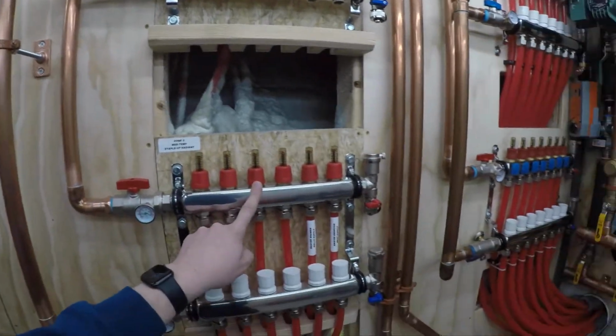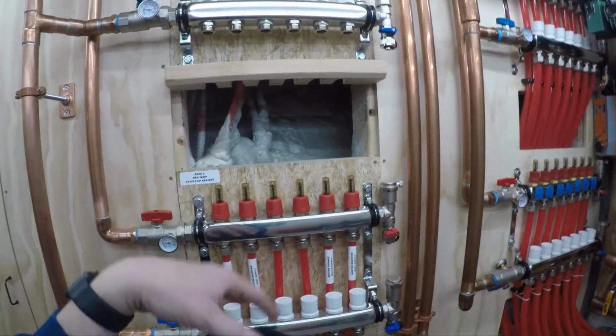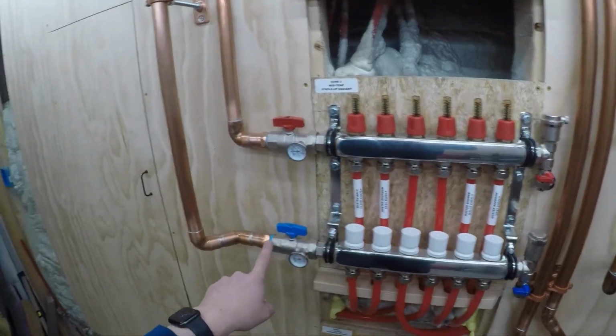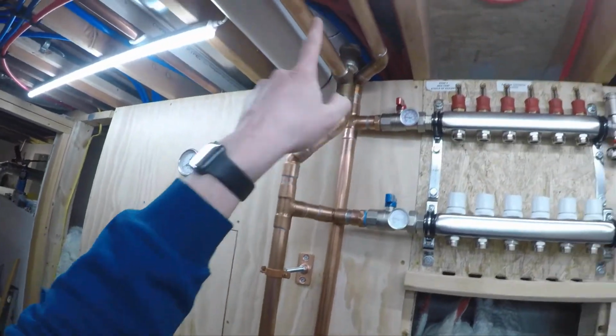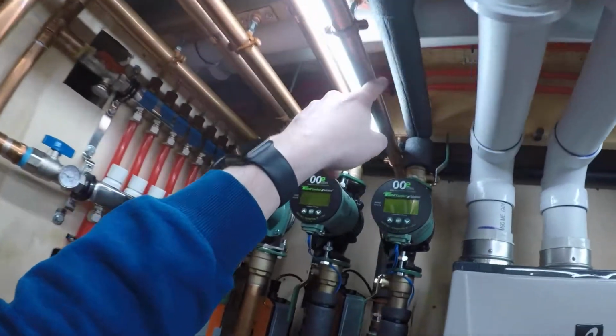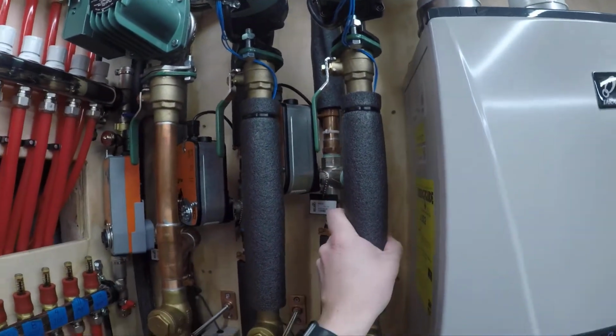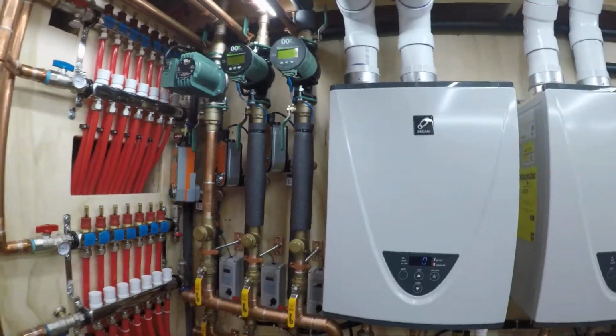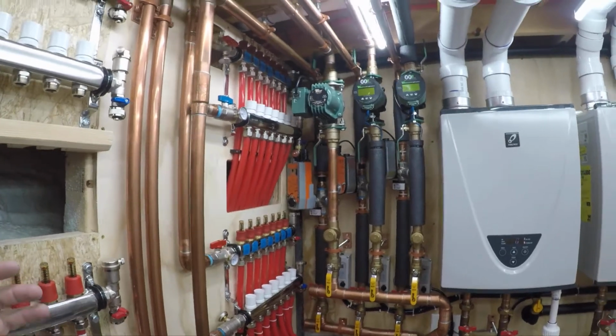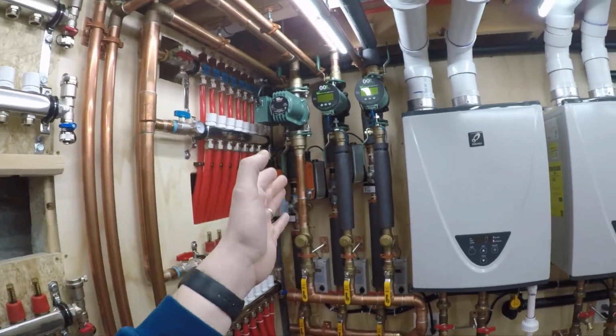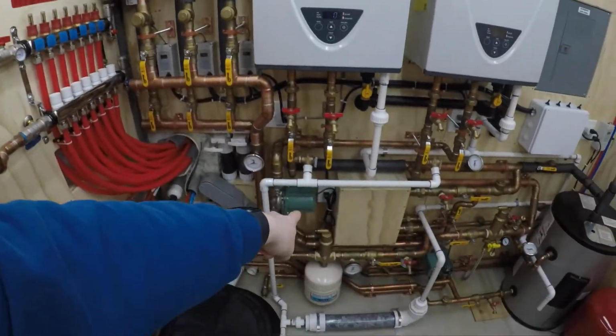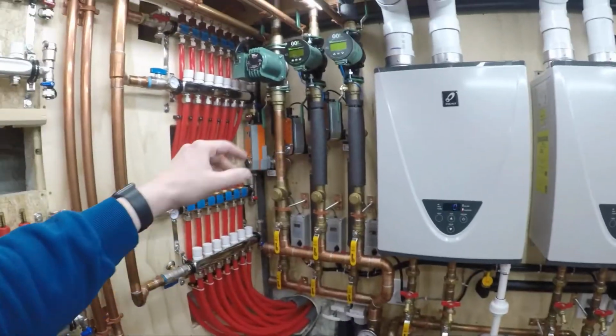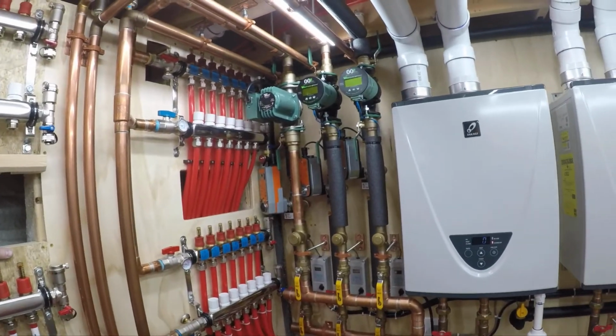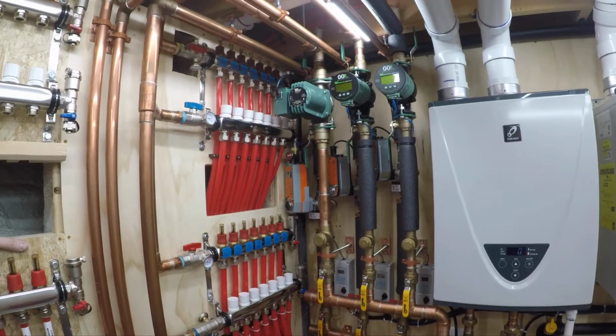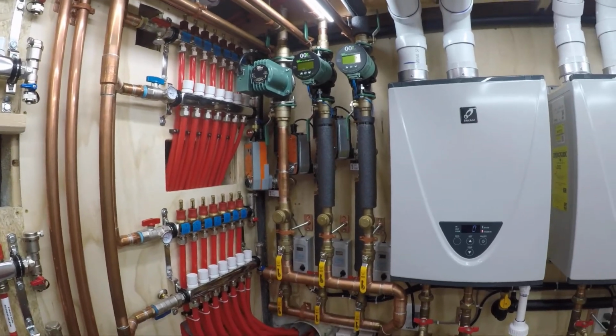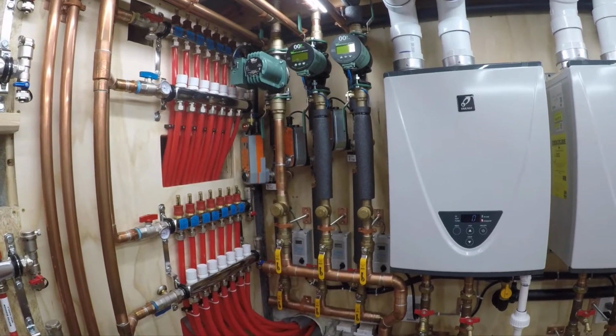Okay, this one's currently hooked up. Go out through the floors, come back through the return. Okay, down. Now the return's in the back. And what I did on these, because now the problem I have is, since any one of these three zones can turn on that pump, what if one of them is calling? What if the Snowmelt's running for hours? You know, which it does. I mean, the Snowmelt could be running for 16 hours.